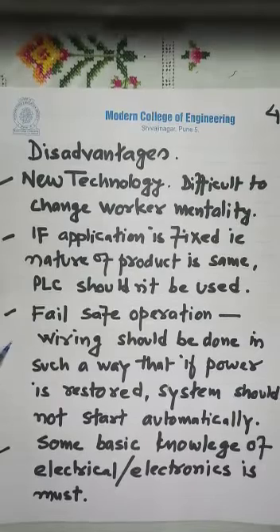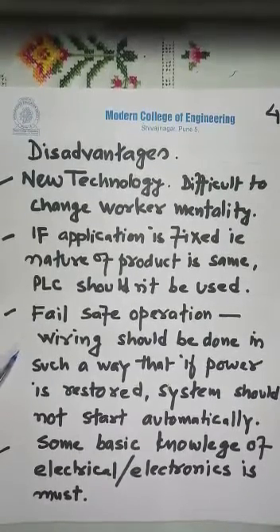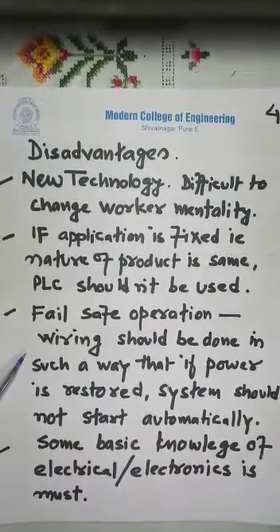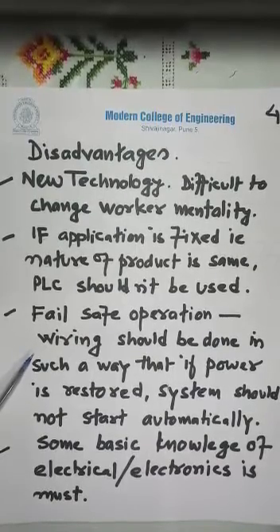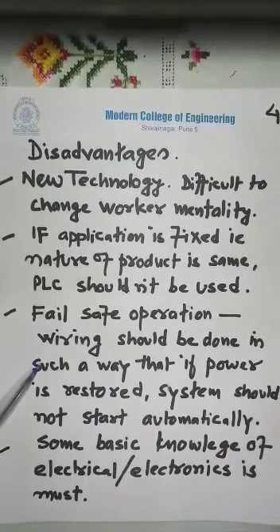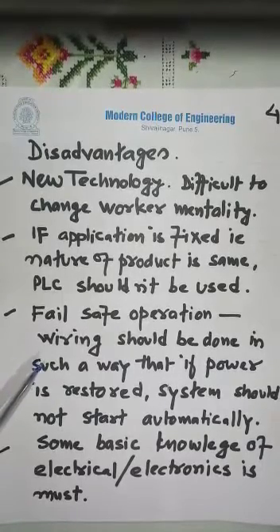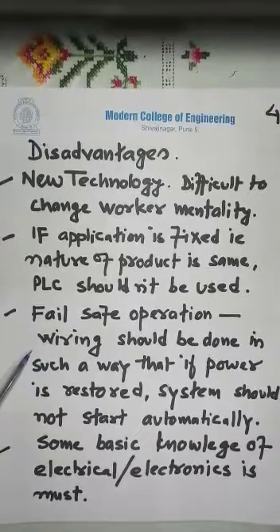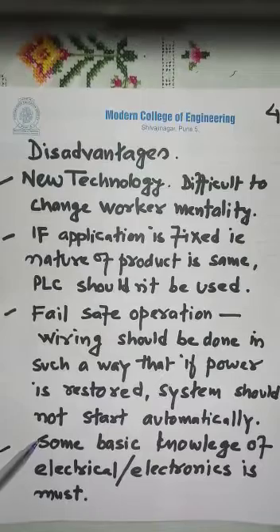One more important point is fail-safe operation. PLC should be programmed such that when a process is ongoing and the power supply fails, then after power is restored, the system should not start on its own — it should start manually. Keeping this in mind, some basic knowledge of electrical and electronics is definitely required for operating any PLC.